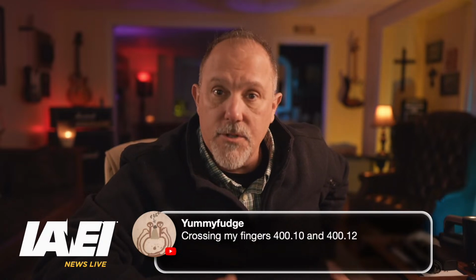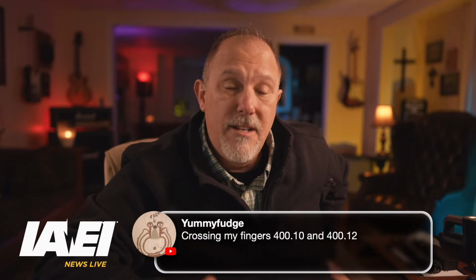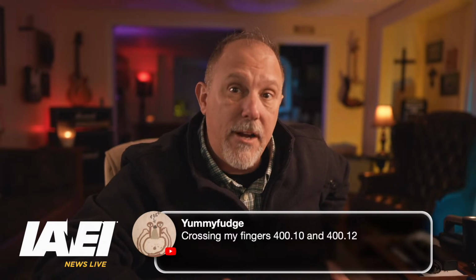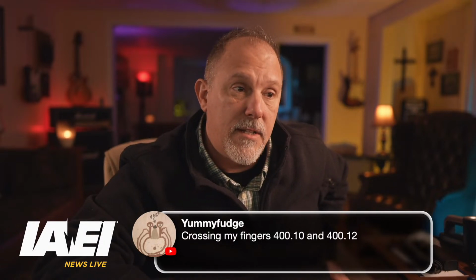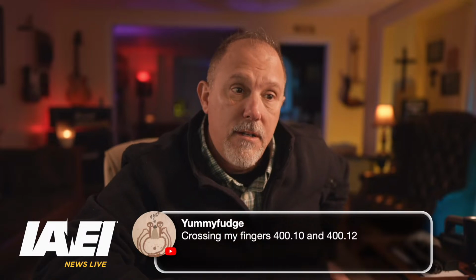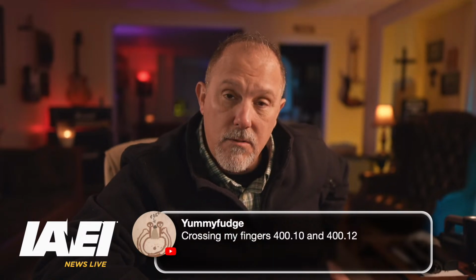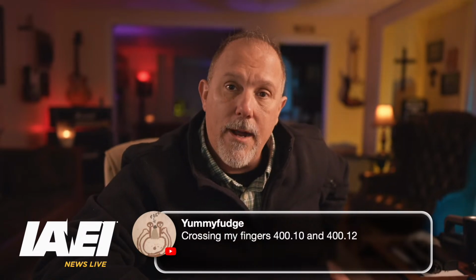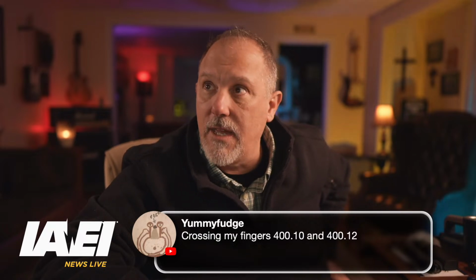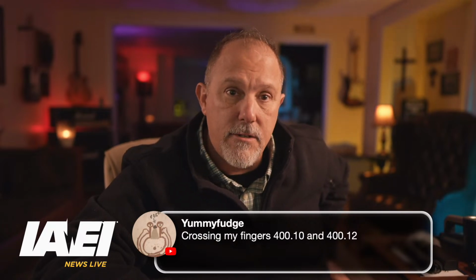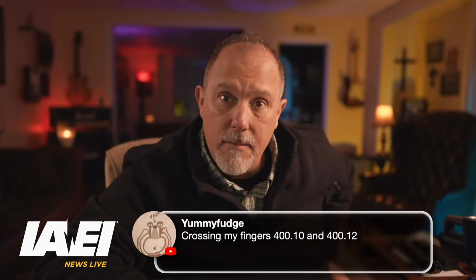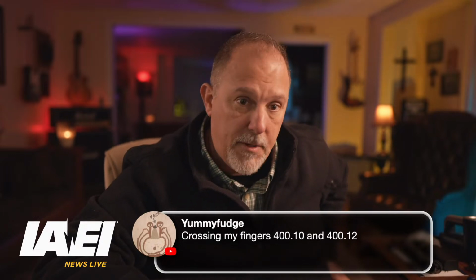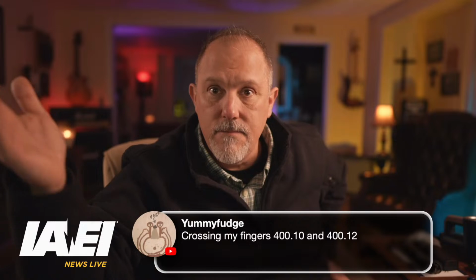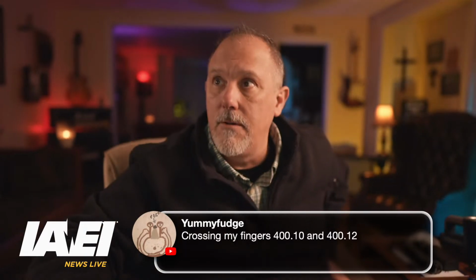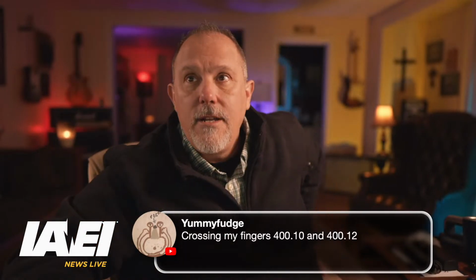Apparently flexible cable is not a defined term. The flexible cord definition is pretty generic — I could even argue NM wire meets the definition of flexible cable, since it's multiple conductors in a flexible sheath. NM cable probably meets that defined term, but we have NM cable specifically, and a specific section in Chapter 3 for that.